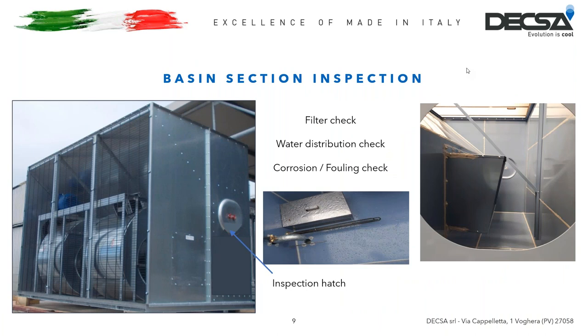With the water in the system always operating — and the motor always off — we can proceed to check that the water falls from the Dexapack filling onto the bottom of the basin. If the rain from the filling falls evenly from all surfaces, it means there is no clogging problem and no dirt problem.